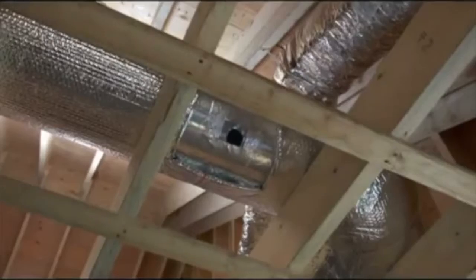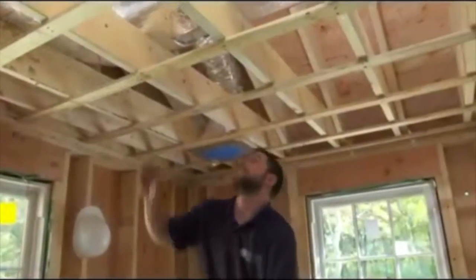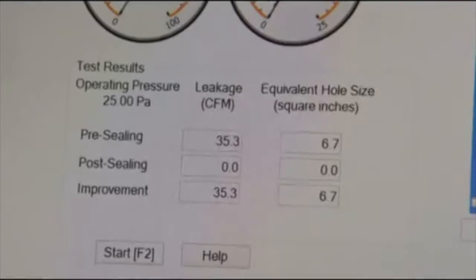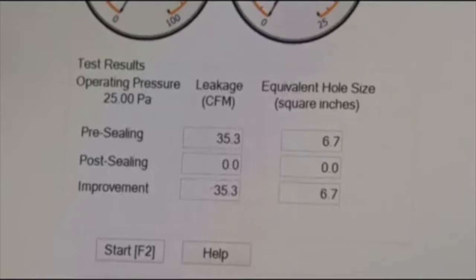Cool. All right, fan shutting down. How'd we do here? Zeros down the board. We got duct leakage of 0 square inches, 0 CFM, 0% of air leakage. Wow, unbelievable. So that is a very efficient system. Not only is it efficient, but now we're not sucking in any air from the attic, any air from the basement when the system's on. We've got great indoor air quality.